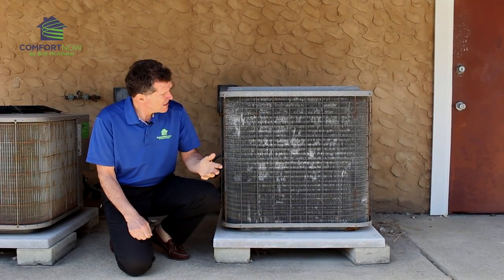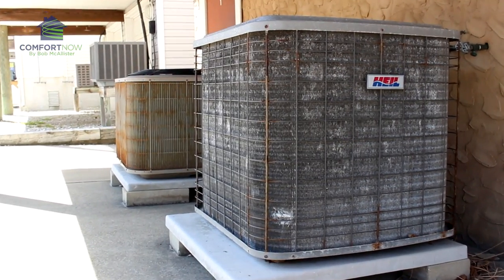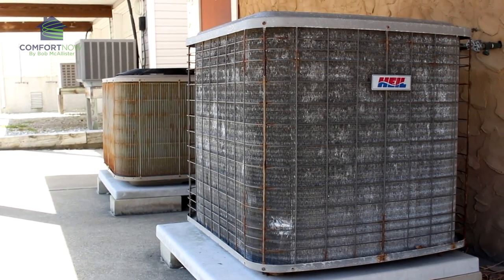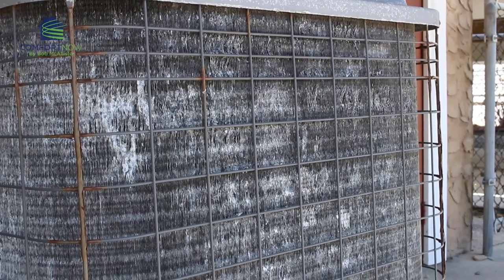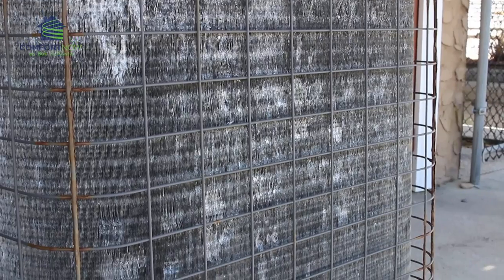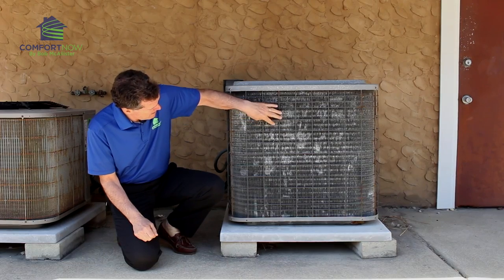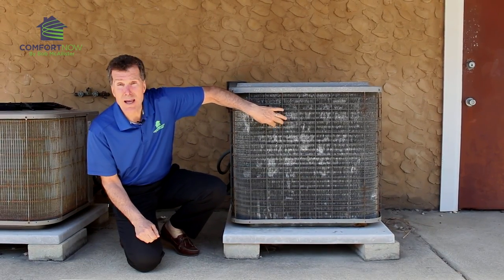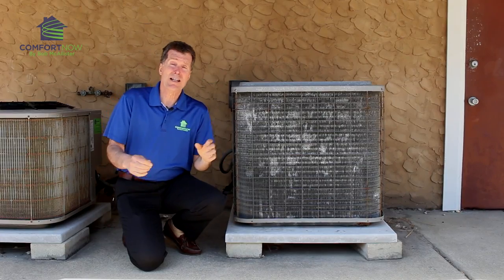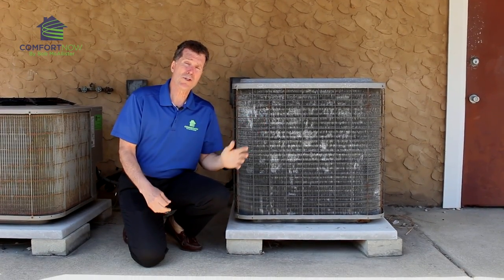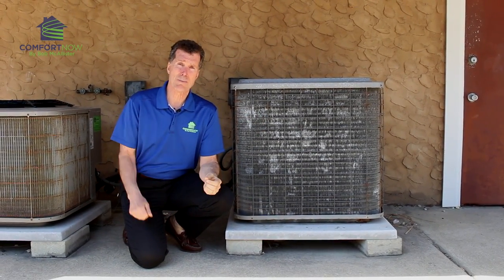Here's a great example. This unit is probably about 10 years old, and salt corrosion is inside. The fins deteriorate and become ineffective, you can see them just flake away. That means they're not even connected to the copper coils running through it anymore, so it can no longer get rid of the heat in the summertime.